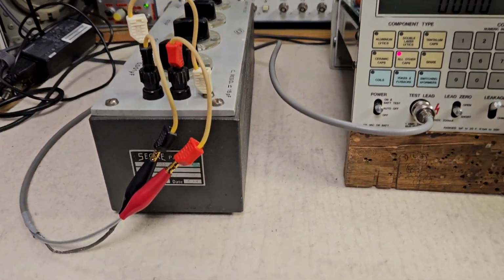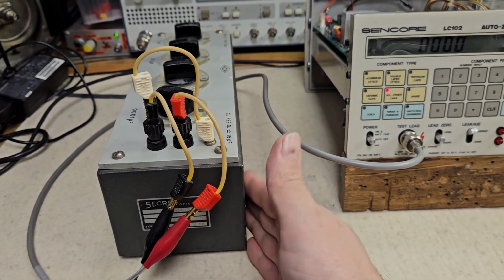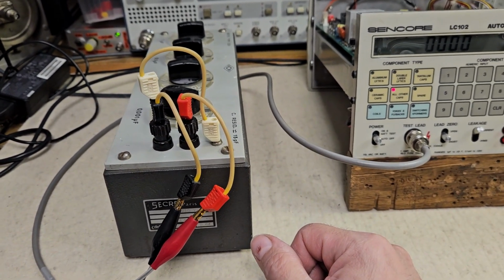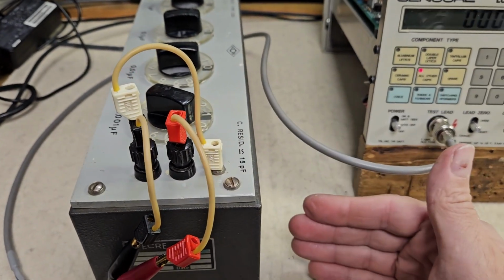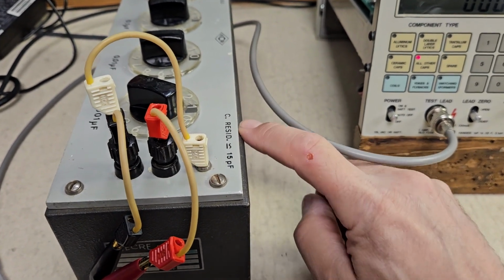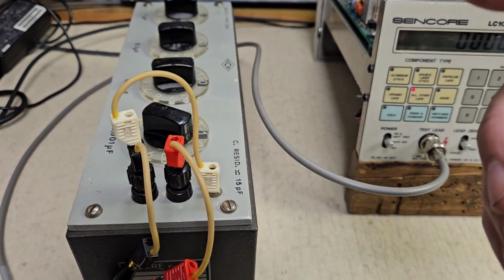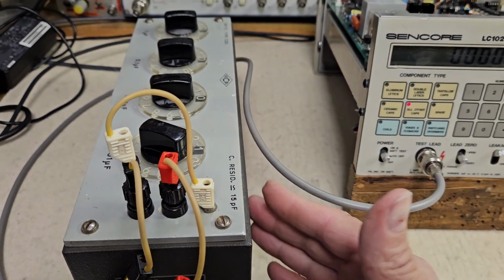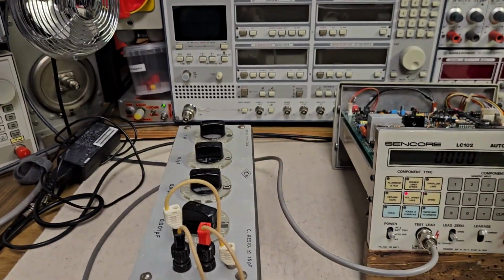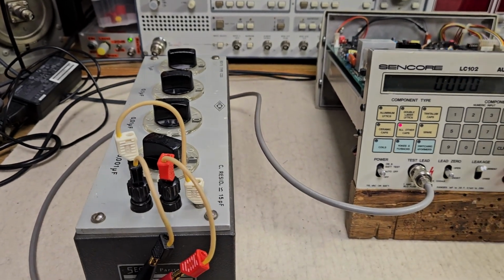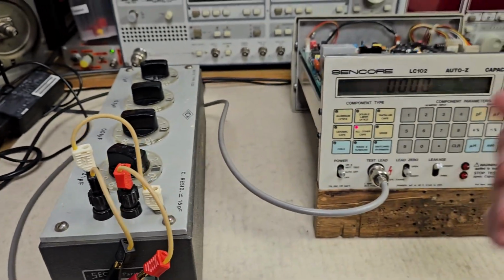I, stupid idiot, forgot to earth or ground the metal shielding here, the metal case. I expected this to be shielded inside, but it isn't actually. It's floating, and they especially specify the residual capacitance here. So it is really a floating device, receiving all the RF interference and hum and all the noise which I have here in the area, collecting it and putting it into the test leads. And this is what caused the variance.